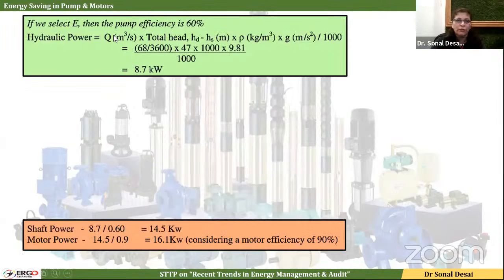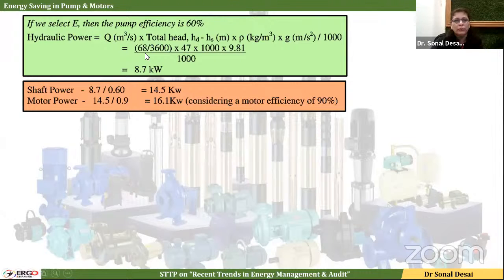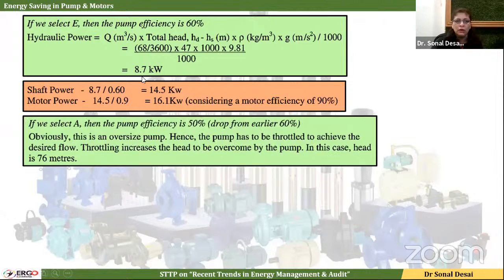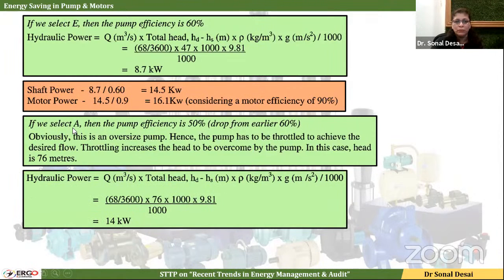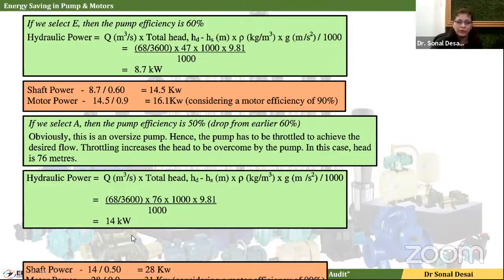So if we summarize the selection of pump E, pump E will be consuming 8.7 kilowatt hydraulic power. If you consider 60% efficiency, it will have a power draw of 14.5 kilowatt. And if you consider the electrical motor efficiency of 90%, then it will have 16.1 kilowatt power consumption. So my selection E will result in 16.1 kilowatt. While if I select pump A, it will have 50% efficiency. So it will draw 28 kilowatt, having a larger size. And ultimately, considering motor efficiency, it will draw 31 kilowatt.